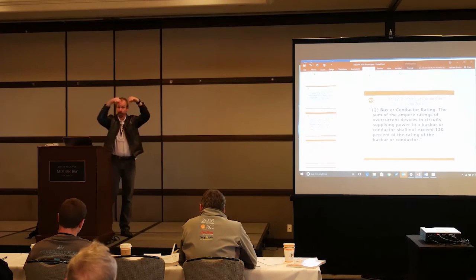Now, if you have two feeds on the same end of a conductor, well, yeah, of course you can have more current flow on that conductor. They got to be both on the same end of the conductor in order to add their current. Opposite end doesn't work. The bigger one always wins. Whichever one is the bigger one, when we do an analysis, the conductor has to be sized for whichever overcurrent device is the larger overcurrent device.